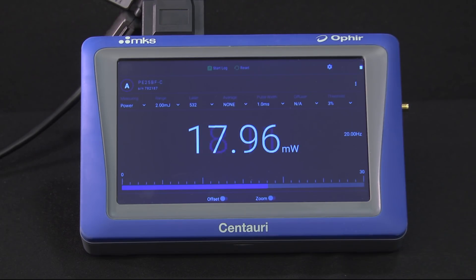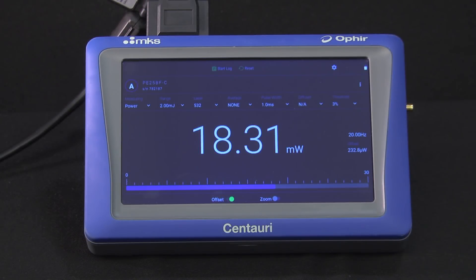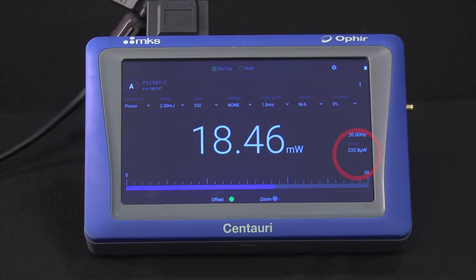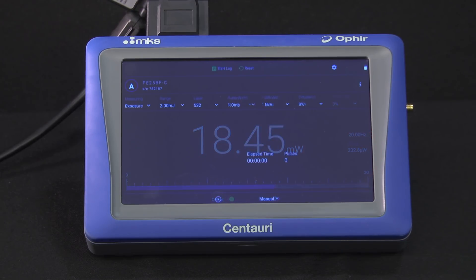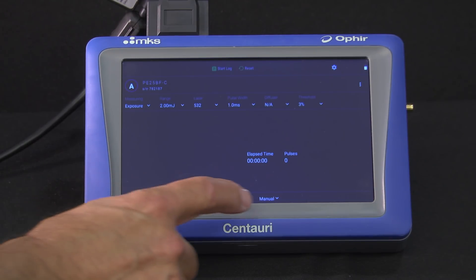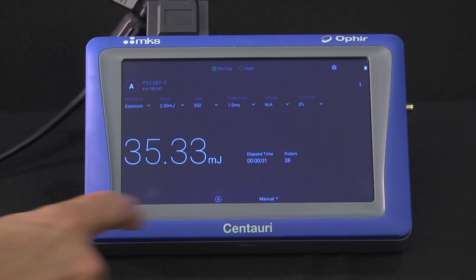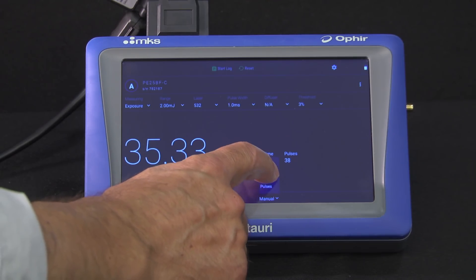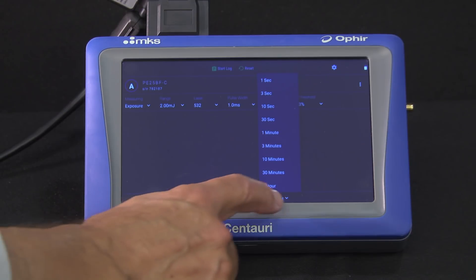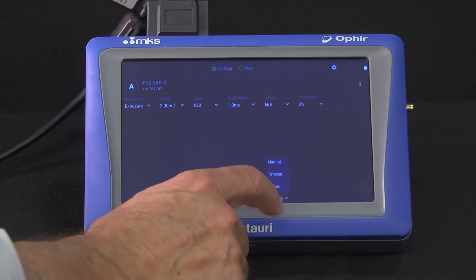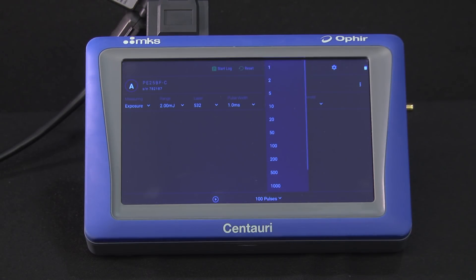Note that offset can only be set when a measurement is actually happening. The value of the offset power — the power that's now being automatically subtracted from all readings — is shown here. In exposure mode, we can measure exposure from when we manually touch start till we touch stop. Alternatively, we can preset the time or the total number of pulses over which we want the exposure measured.